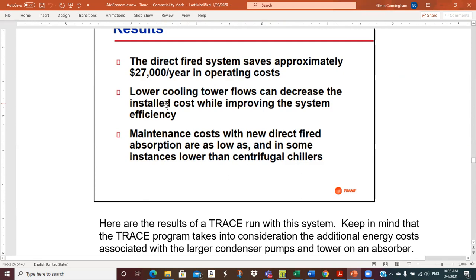But then later on in the slides, they're talking about some of the new Trane absorbers that don't need as much condenser water as the industry standard. And so the Trane absorbers can reduce cooling tower flows. But if you're just comparing centrifugal to absorbers, even the Trane absorber, you have to provide more cooling tower flow for the given capacity chillers. So that middle bullet, I think, is a little misleading.